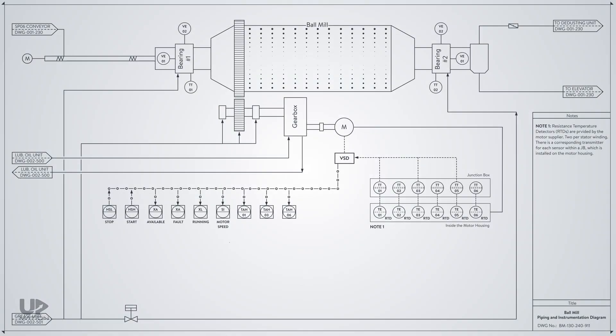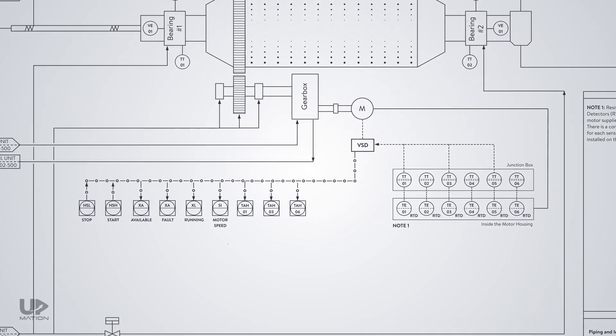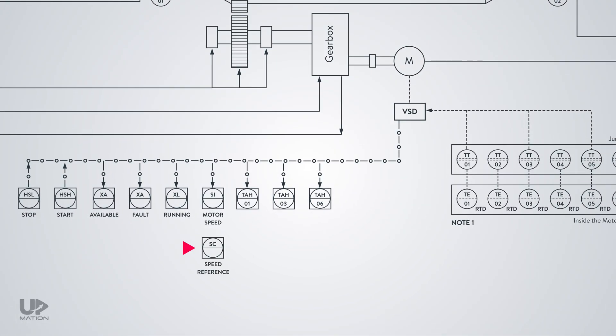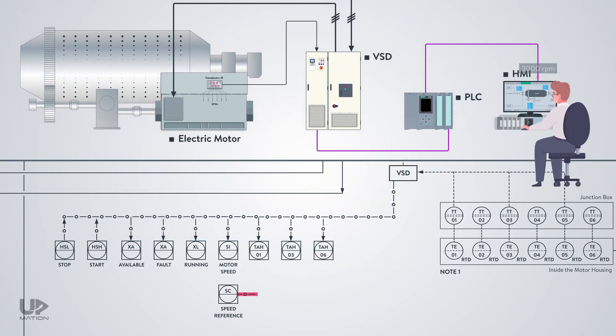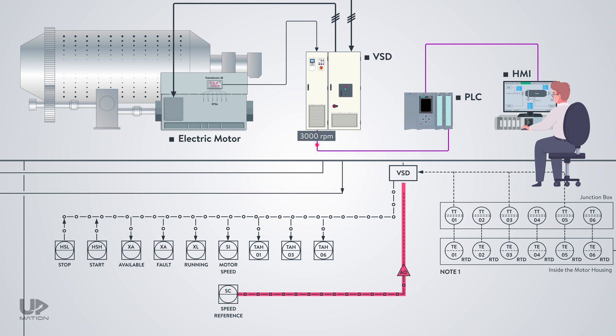The other piece of data that the VSD should receive from the control system is the motor speed reference. The operator will enter the desired speed in the human-machine interface. This speed reference will be processed in the PLC logic and, through a high-speed analog output card, will be sent to the VSD.